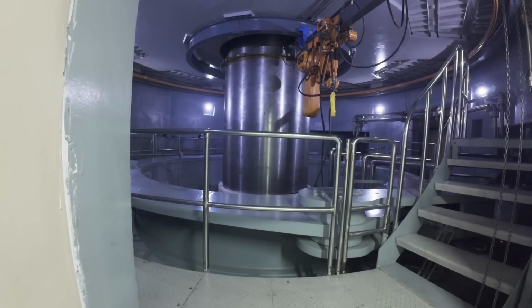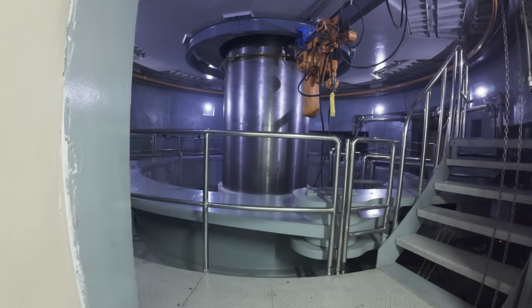Now, the startup enters its most dramatic phase, turbine acceleration. The digital turbine governor carefully commands the hydraulic servo motor connected to the wicket gate. Very slowly, the wicket gate begins opening. Controlled water flow enters the runner, and for the first time during startup, the turbine shaft begins to rotate.